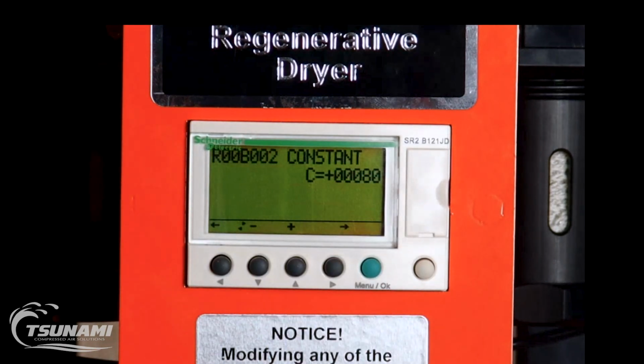So if we have a pressure transducer inside the PLC and we pull a signal, what this says is 80 pounds of pressure is where we're going to turn the dryer on or turn it off when it hits that value. So that's one. Our PLCs are also configured so that we can have multiple inputs regarding pressure. So if I hit the block arrow up to 3, 3 is also another pressure setting.